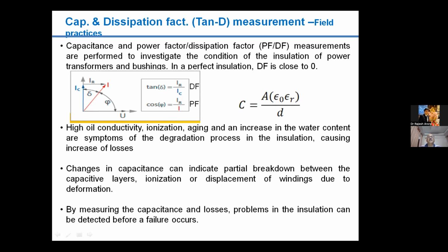Tan delta is nothing but the ratio of the resistive or loss component of the current to the capacitive current. Whenever you charge the capacitor, or inject voltage into the test sample, the total current has a very small loss component and a high capacitive component. The ratio of the resistive component to the capacitive component of the current is known as tan delta, whereas the ratio of the loss component to the total current is known as the cosine, or the power factor.